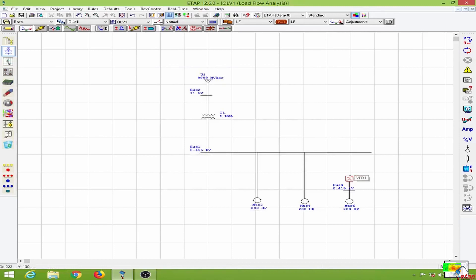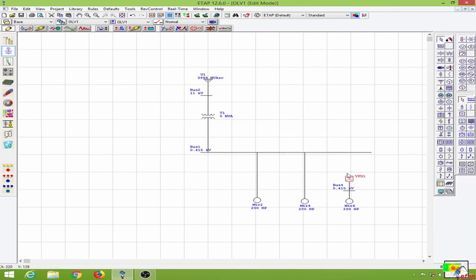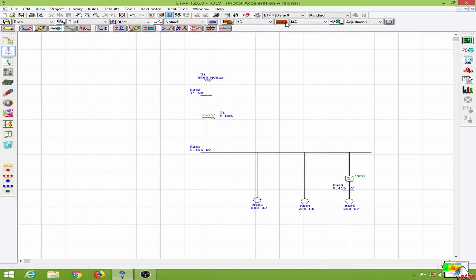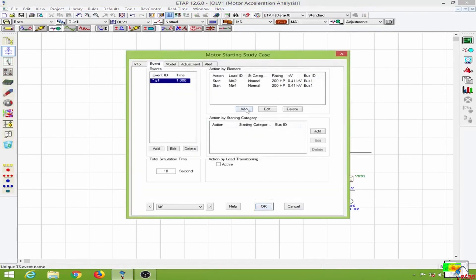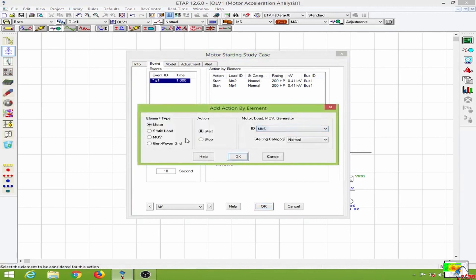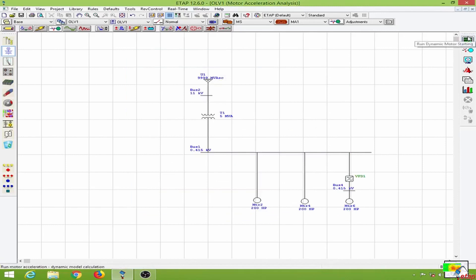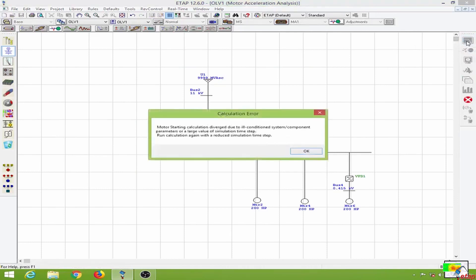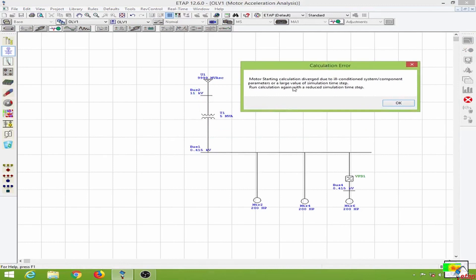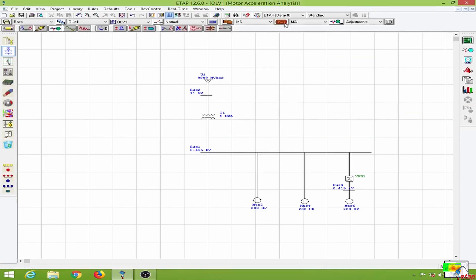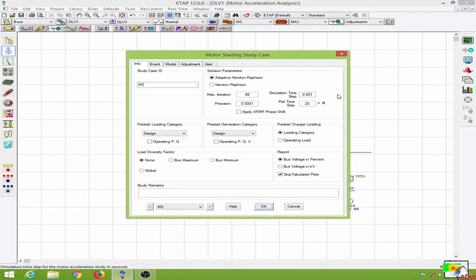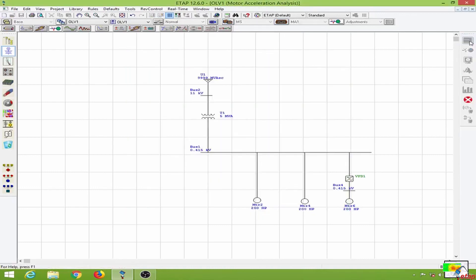I will connect my V/F drive to this bus, then let us conduct the motor acceleration analysis. Let me go to the edit study case option, then I will add motor 6 and the action will be to start. Let us conduct the dynamic motor acceleration study. It has started to show some errors — we will have to reduce the simulation time step. We will go over here, reduce the simulation time step, click OK, and run this again.